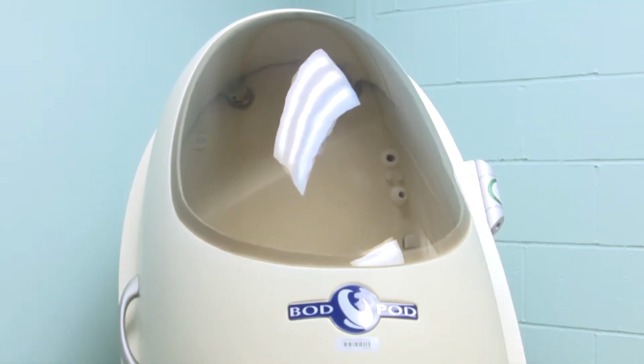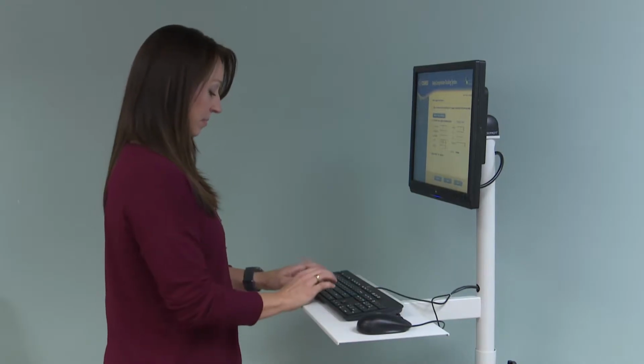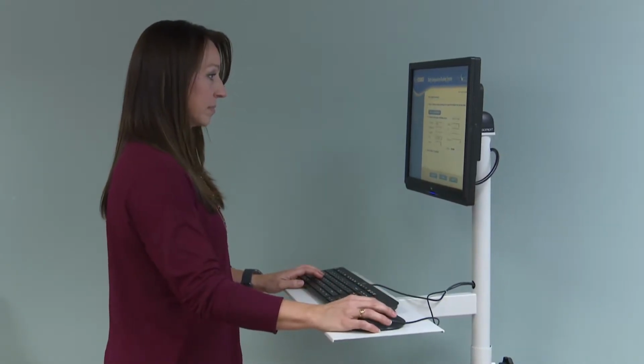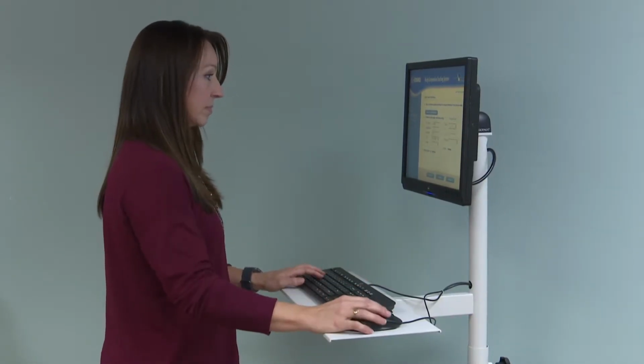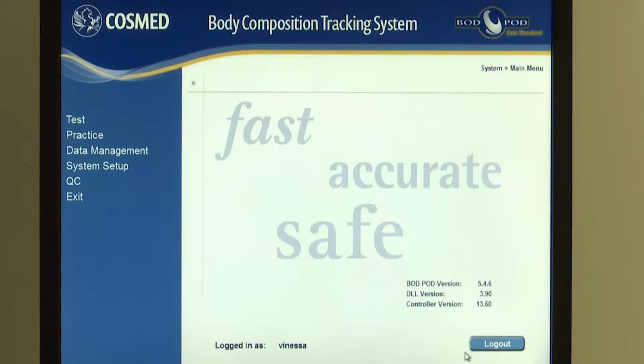On the main screen, you will see 6 options to choose from on the left side of the screen. Test. This is used when it is time to conduct a test. Practice. When practice is needed with certain aspects of the Bod Pod and we do not want to skew a client's test results. Data management. This allows any information to be fixed that was entered incorrectly prior to the test, for example, birth date or height.